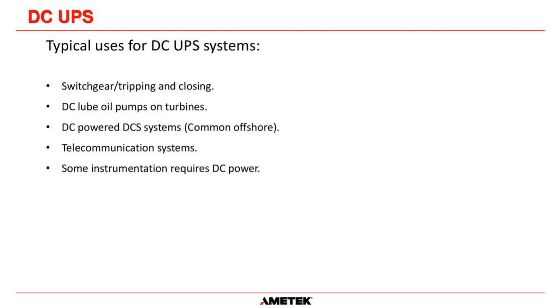Okay. The other one is DC Lube pumps on turbines, which I mentioned earlier. Most turbines will have an AC Lube pump. So if for some reason the turbine goes offline and starts to slow down, you have to keep the bearings in that turbine lubricated to make sure that they do not overheat and eventually fail and cause the whole turbine shaft to bend, warp, and it can cause millions of dollars worth of damage to a turbine. So you have to have some system there that if the AC fails, that there is a pump that will pump the oil through the turbines even when you lose AC power. And that's what a DC Lube pump is. And they are extremely critical to protect turbines from basically blowing themselves to pieces when they are going through their cool down cycle.